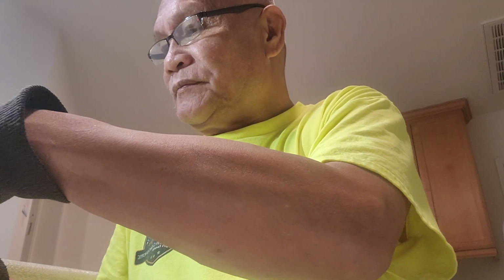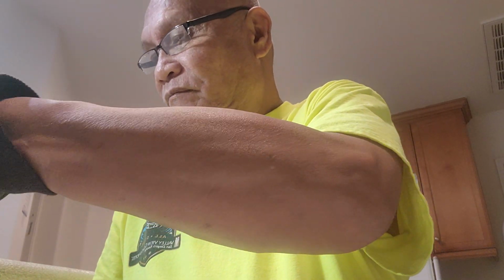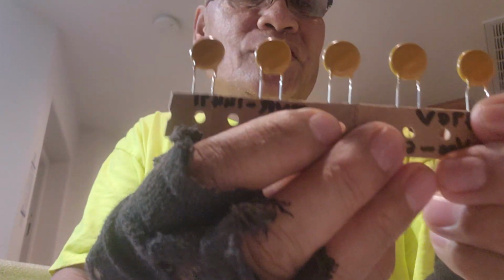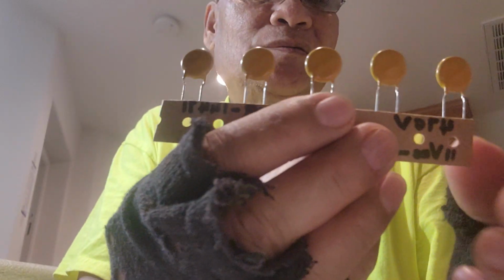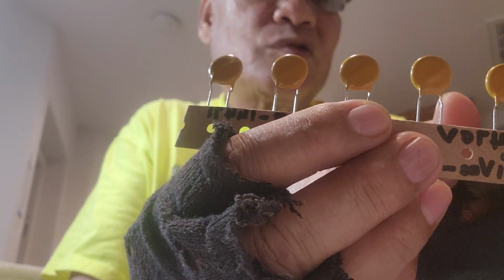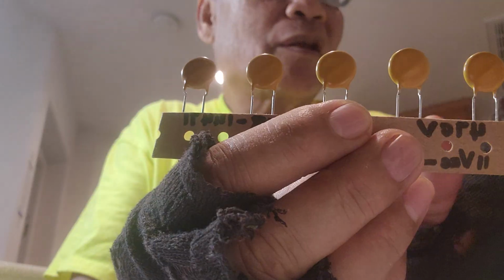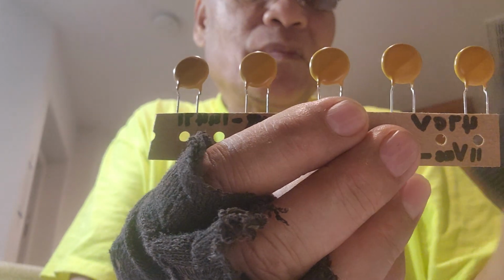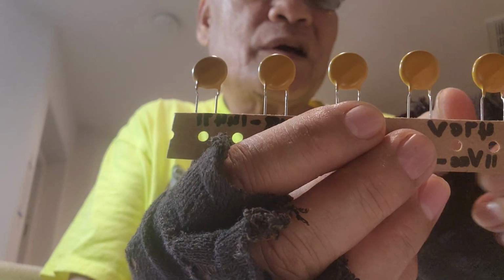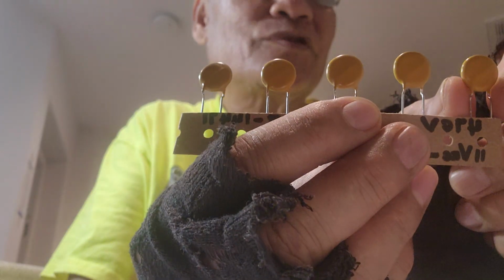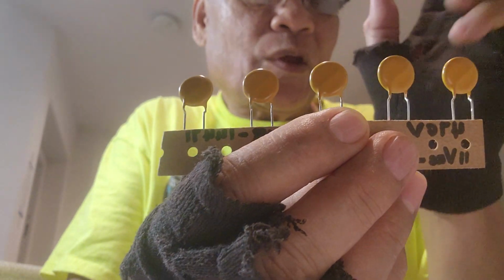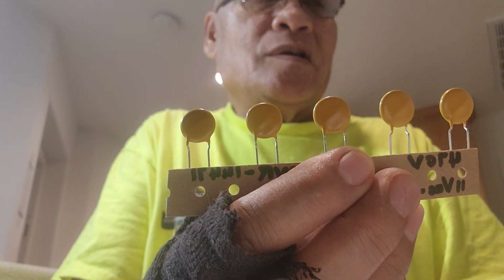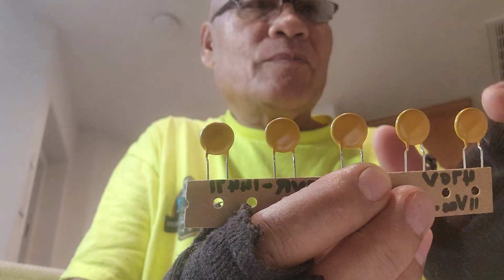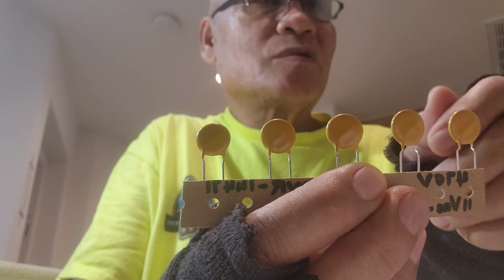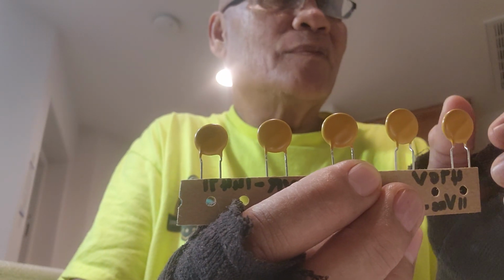So the important thing here is: when the metal oxide varistor is good, the resistance between the terminals should be open, or in the range of million ohms—7 million or 11 million will be fine. But if it reads OL or open circuit, that's even better when you test it. So now we know the importance of the metal oxide varistor, or simply a surge protector.